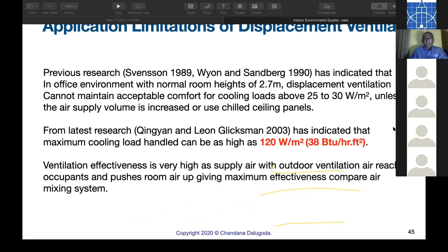Previous research during the 90s indicated that in an office environment with normal room heights, displacement ventilation cannot maintain acceptable comfort for cooling loads above 25 to 30 watts per square meter, very, very low values, unless the air supply is increased or chilled ceilings are used in combination. But the latest research in 2003 has indicated that the maximum cooling load handled can be as high as 120 watts per square meter. If we convert that to IP, it is 38 BTU per hour per square foot. Now, this is a good milestone.